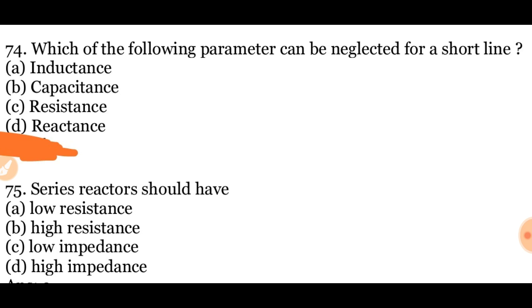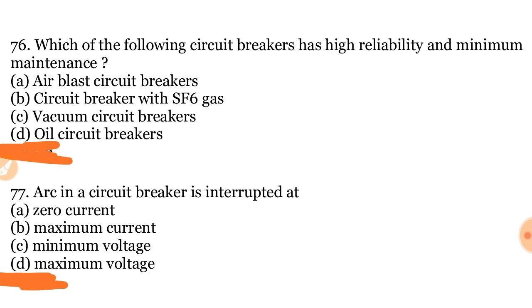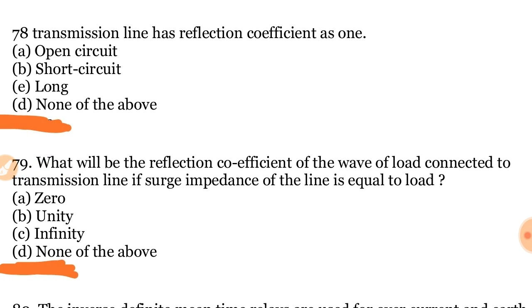75 question. Series reactors should have low resistance, high resistance, low impedance, high impedance. Answer is low resistance. 76 question. Which of the following circuit breaker has high reliability and minimum maintenance? Air blast circuit breaker, circuit breaker with SF6 gas, vacuum circuit breaker, oil circuit breakers. Answer is circuit breaker with SF6 gas. 77 question. Arc in a circuit breaker is interrupted at zero current, maximum current, minimum voltage, maximum voltage. Answer is zero current.